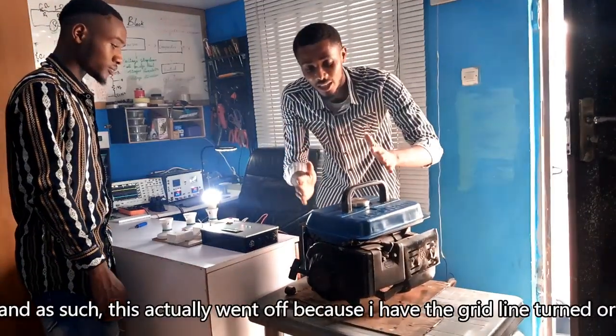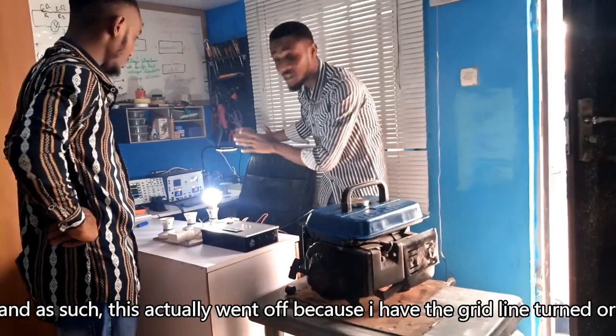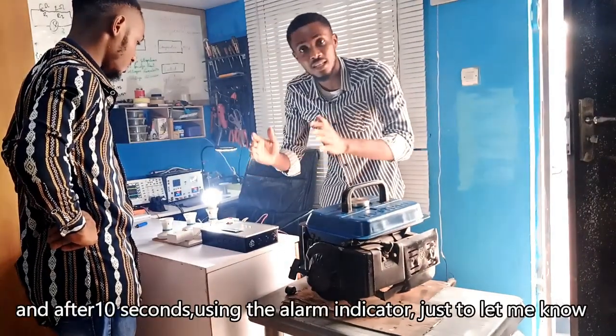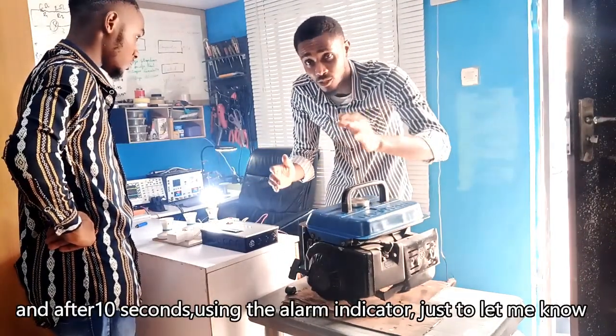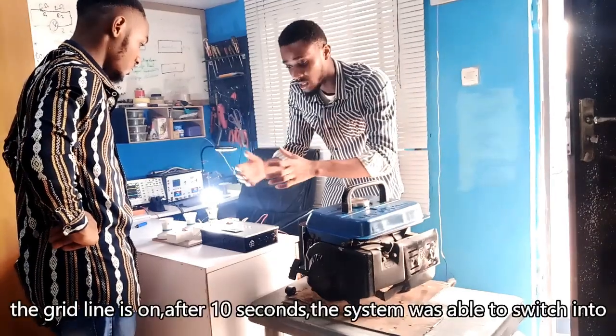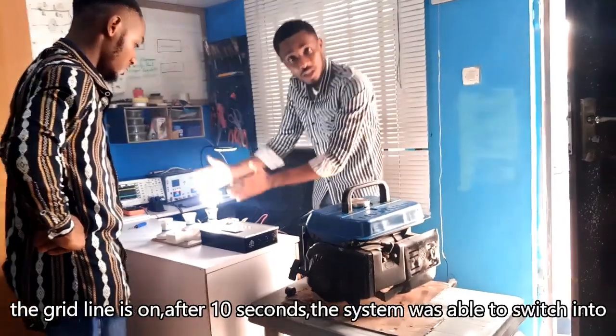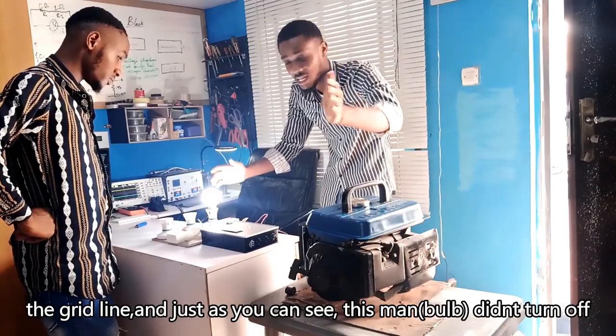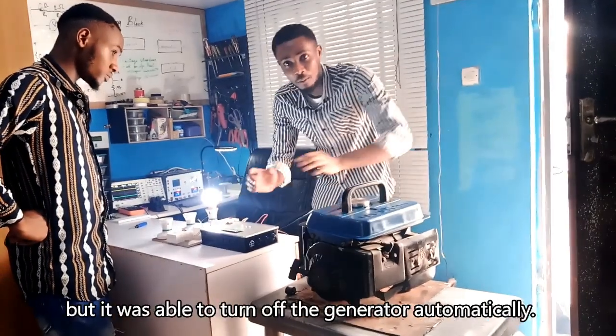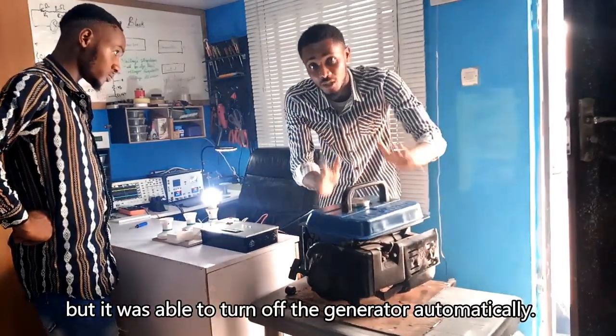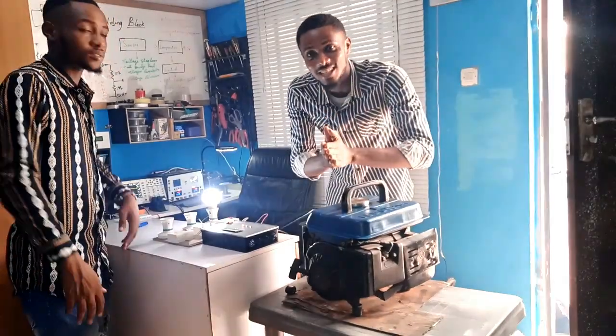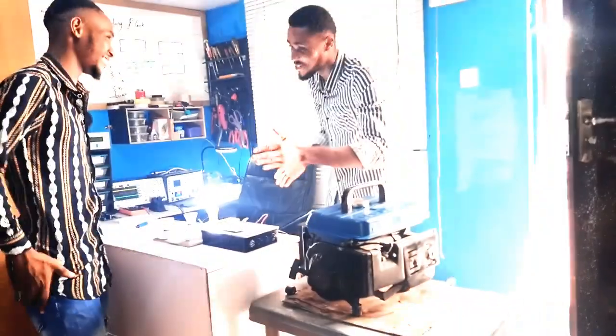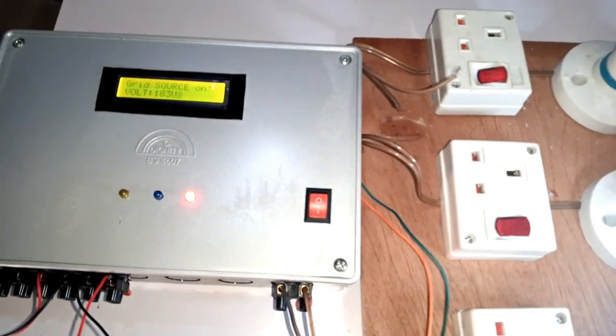And as such, this actually went off because I have the grid line turned on, and after 10 seconds using the alarm indicator just to let me know that the grid line is on, the system was able to switch into the grid line, and just as you can see, the bulb didn't turn off, but it was able to turn off the generator automatically, and that is the system working, and I'm so excited to have completed this project. I'm excited at the outcome.